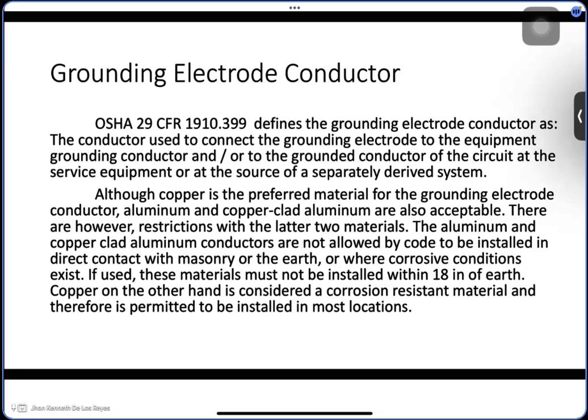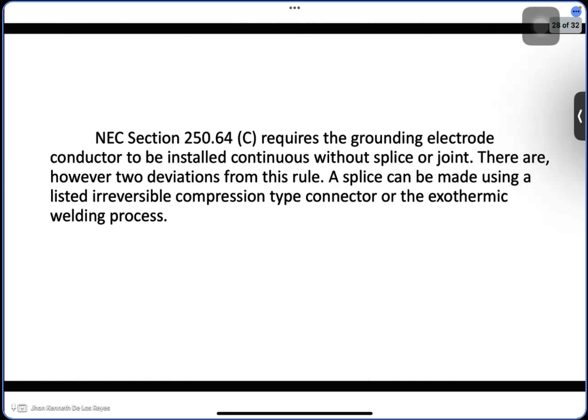Aluminum cannot be buried or placed close to or in contact with masonry due to corrosion. In short, the GEC, or grounding electrode conductor, must be continuous, properly sized, and preferably copper should be used, though aluminum is used most of the time.